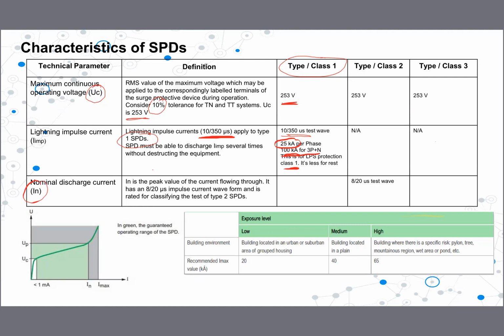Nominal discharge current mostly applies to type 2 SPDs. That is the current flowing through the SPD, right? Now here in this graph, you can see this is the IN, right? This is the maximum safe current that can flow through this SPD. In certain products, they are talking about Imax as well, right? Imax is the maximum current, but mostly we use IN, that is the maximum safe current which can pass through the surge protection device, right?